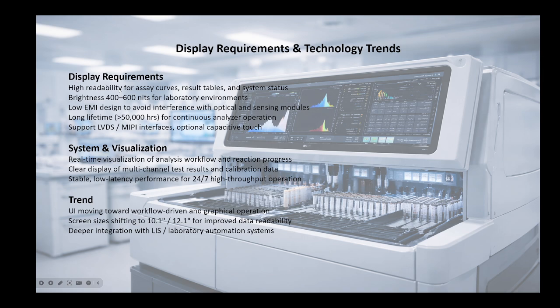Display requirements: high readability displays must clearly present assay curves, results tables and system status. And low EMI design is critical to avoid interference with optical and electrochemical sensing modules. The touch surface must also withstand frequent alcohol cleaning without degradation.